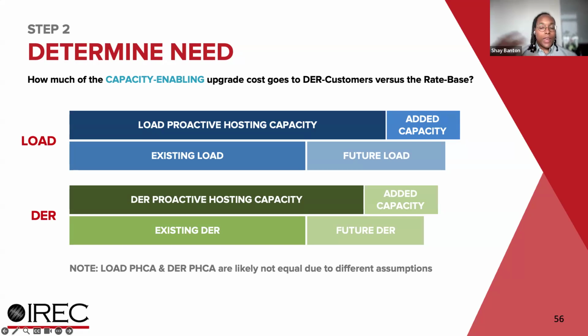Moving on to DER, the same thing applies. We assess what the DER host capacity is—how much DER the system can accommodate. Because they have different inputs, DER host capacity is likely smaller and different, which is why that bar looks a bit different than load proactive host capacity. So you have the capacity of the system, existing DER that hasn't exceeded that threshold, and future DER that does exceed it—therefore you need added capacity. Both added capacity values exceed what future load and future DER actually need, because you don't build up to exactly the value required; equipment comes in standard sizes, so it's likely to exceed it by some amount. As mentioned, load PHCA and DER PHCA are likely not equal due to different assumptions.